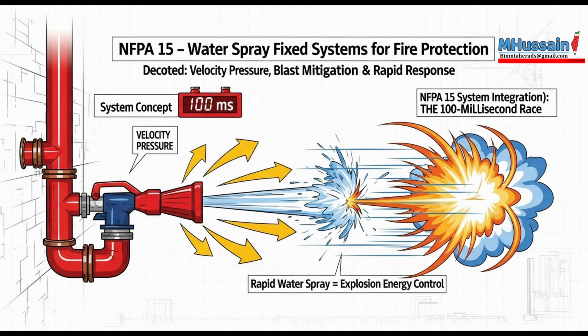It does. The standard lists 5 critical categories for acceptable applications. First up, gaseous and liquid flammable materials. Think storage tanks, process lines, loading racks. Second, specialized electrical hazards. And this is where that precision spray becomes absolutely paramount, protecting huge oil-filled transformers, switchgear, motors, even extensive cable trays where the fire is fueled by insulating oil or just heavy electrical load. Right, and spraying water onto electrical gear, that automatically raises the stakes, doesn't it? You need specific patterns, fast activation. Absolutely. Non-conductive patterns are key.